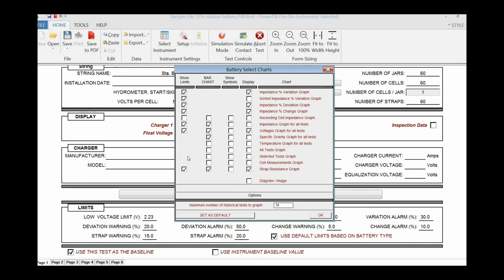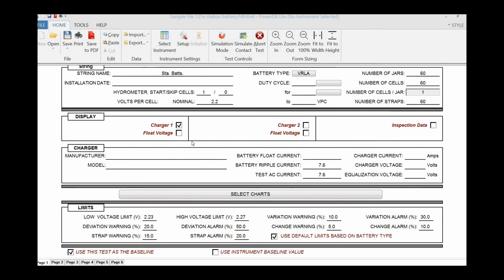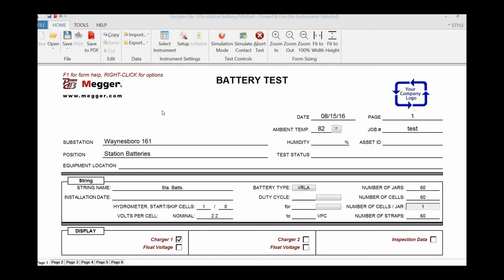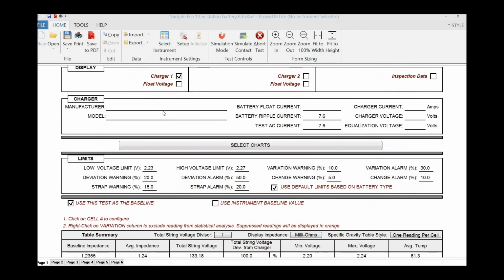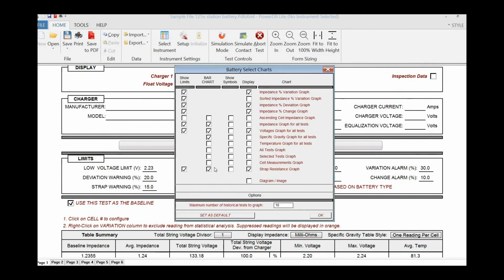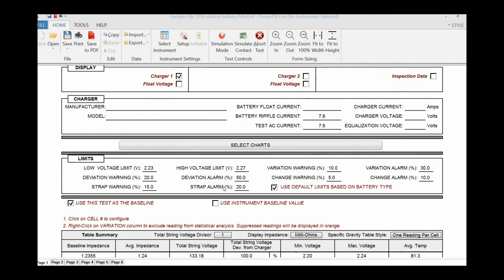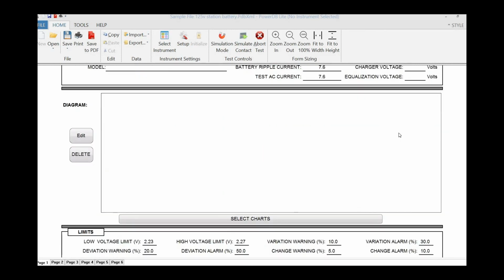I can also choose to show the graphs within the limit lines, so I can see which cells pass and which fail. These settings can be made as the default settings, making these the default charts that will be on every report I make. When I'm done, I simply click OK. To add an image to the report, scroll down and click on the Select Charts button, then enable Diagram/Image and select OK. You can now paste the image into the report.